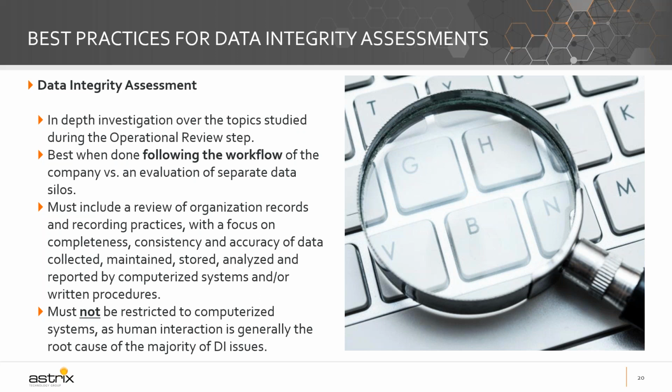So it must include a review of organizational records and recording practices. We will focus again on the ALCOA definition to see if data is accurate, consistent, maintained, stored, analyzed and reported the way procedures say it should be done. And it must not be restricted to computerized systems, as human interaction is generally the root cause of the majority of the data integrity issues.